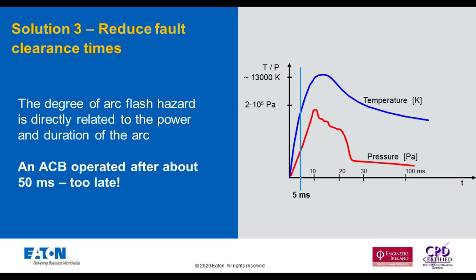In a compact switchgear assembly, the pressure can obviously increase rapidly to a point where the enclosure can't contain it, and the hot gases caused by the arc escape from the weakest points of the enclosure. They bend doors, blow doors off, bend side panels, and impact the IP rating of the assembly and the safety of the enclosure, in terms of people potentially being able to touch live parts inside the assembly.